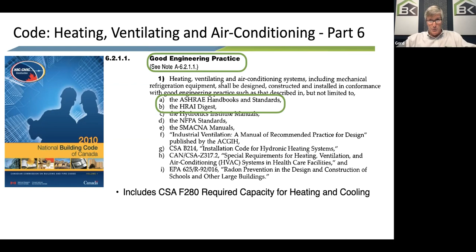You still have to follow good engineering practice. You can't say the code doesn't mention cooling so I don't have to meet any specific requirement - no, you're still subject to the metrics in the ASHRAE handbooks and the HRAI Digest. Although I wanted to make sure - this page doesn't show the CSA F280 standard for required capacity for heating and cooling, but it is mentioned in other sections of the code. So the code, as Robert said, is a starting point in terms of a number, but it certainly wouldn't help you define comfort for all of your occupants, which is where we want to head.